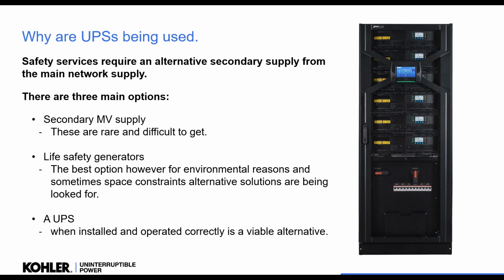And this is where we're seeing the UPSs being used a lot more. So obviously, we need a secondary supply. The main one to have, if possible, is a secondary mains supply. And then we have the life safety generators, which again is the next best option. If we haven't got a supply, or we can't use the generator, then we will look at using a UPS. Now this, when installed and operated correctly, is a very viable alternative.